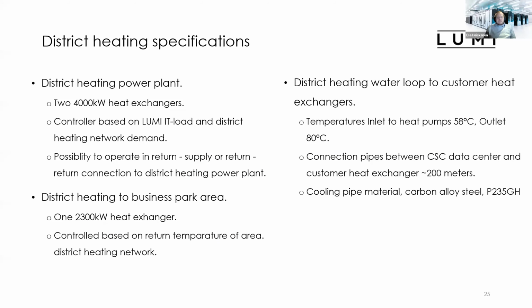So the district heating specifications quickly: for the district heating power plant, we have two 4-megawatt heat exchangers. So we are able to provide up to 8 megawatts of district heating to the City of Kajaani district heating network, which is connected to this district heating power plant. And this is controlled based on the Lumi's IT load and district heating network demand. And we can operate in two different ways for the district heating power plant.